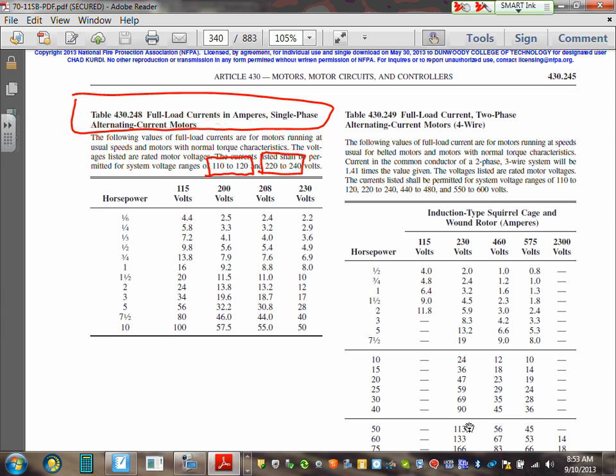Do you see why? The voltage that I have is 240. So my 240 is close to what? Is it close to 208, 200, or 115? 230 is closer. So for my 240 volt system, my motors 99% of the time will be rated for 230. Here's what they do for motors, guys. The system voltage is 240. By the time you pull the conductors all the way up here, they're still going to lose voltage, right? They rate the equipment for 230. So they allow you 10 volts to lose along the way, and the equipment continues to operate properly. So that's why the system voltage is slightly larger than the equipment voltage, slightly, not a lot.